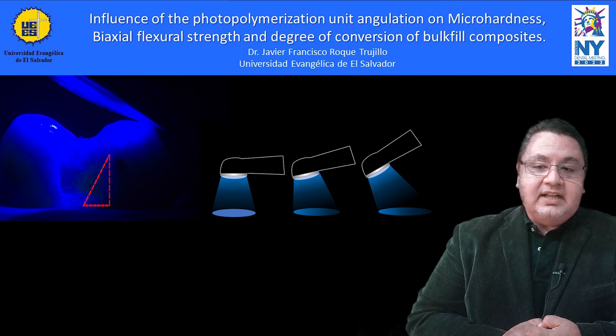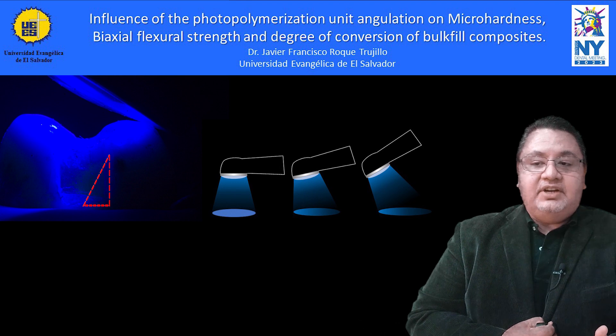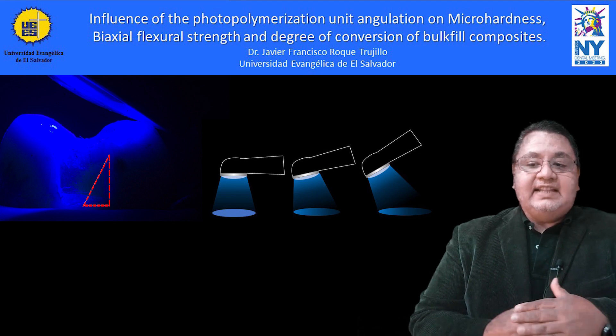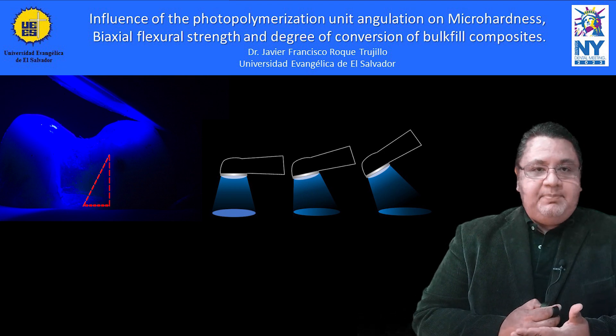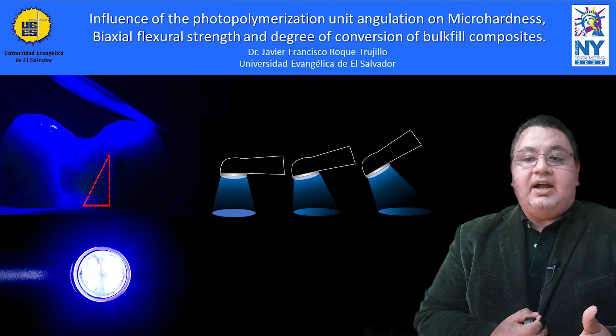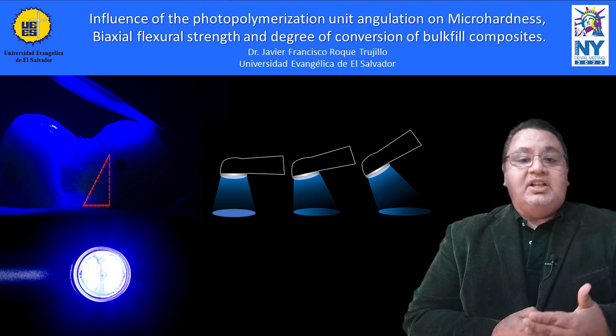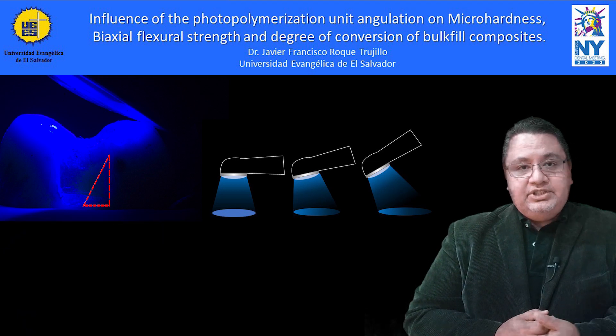It must be taken into account that the cavity configuration may create shadow areas or zones without coverage of the light beam because of wall disposition, due to the dispersion that occurs as the light tilts, mainly affecting the internal or deepest part of the cavity preparation. An angled light-curing unit allows light to penetrate the deepest area of the cavity preparation, so clinicians should take into account — besides its irradiant power — its design, which allows accurate positioning of the tip in reduced-space situations such as in posterior teeth.